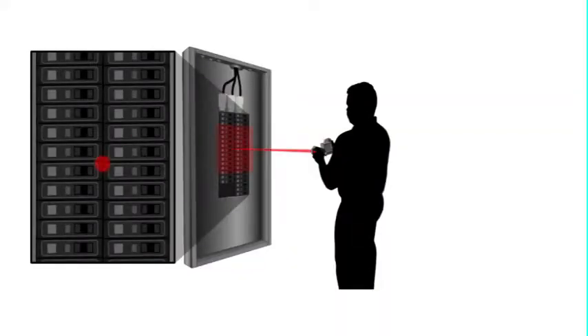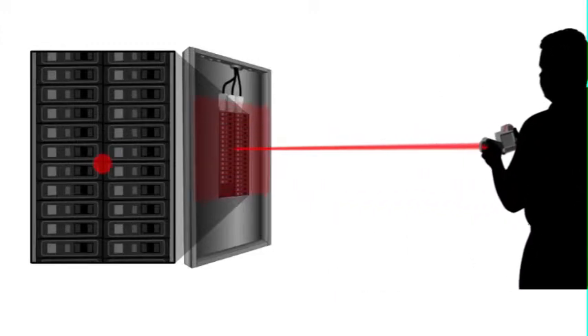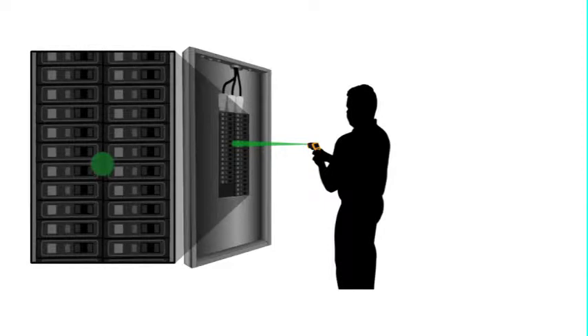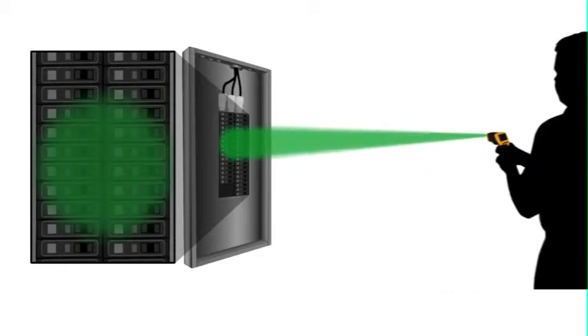With the FLIR, you can accurately measure targets as small as one-half inch from over 60 feet away. But with a temperature gun, you have to be within inches of the thing you're trying to measure to get an accurate reading. The farther away you are, the less accurate your readings get.